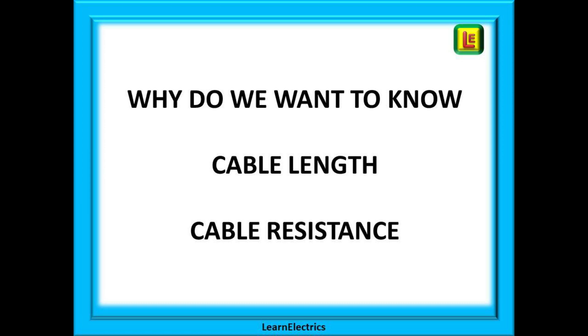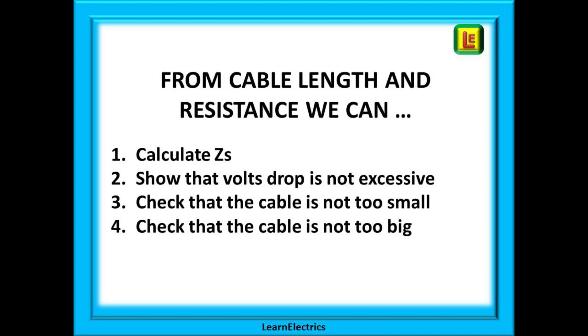Let us look at a frequently asked question which is why do we want to know the cable length and the cable resistance? If we know both these values we can determine R1 plus R2 and from that we can calculate ZS. ZS as you know is one of the checks that we do to be certain that the breakers and fuses will operate correctly and protect the occupants of the building.